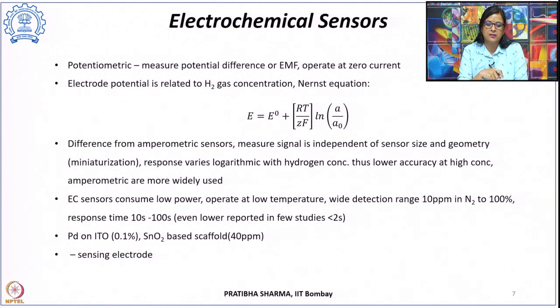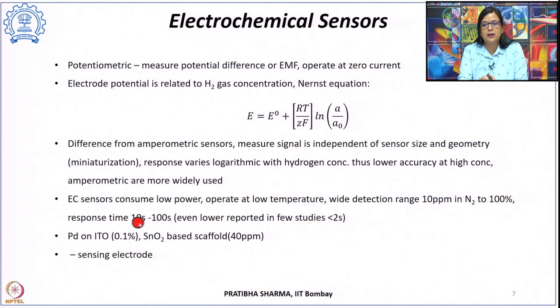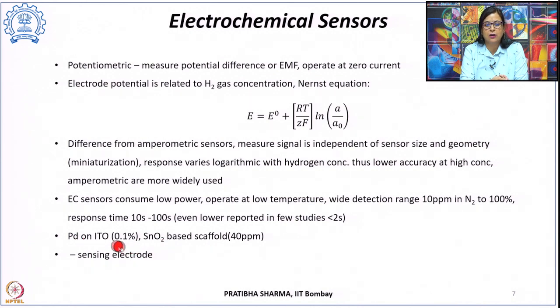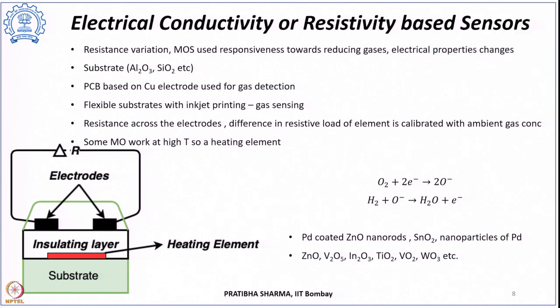The advantages of electrochemical sensors are lower power consumption, operation at lower temperature, and wide detection range from around 10 ppm in nitrogen to 100%. Response time is typically 10 to 100 seconds, though some reports show as low as 2 seconds. Materials like palladium on ITO give a limit of detection of 0.1%, while tin oxide-based scaffolds can operate at higher temperatures with a detection limit of 40 ppm.